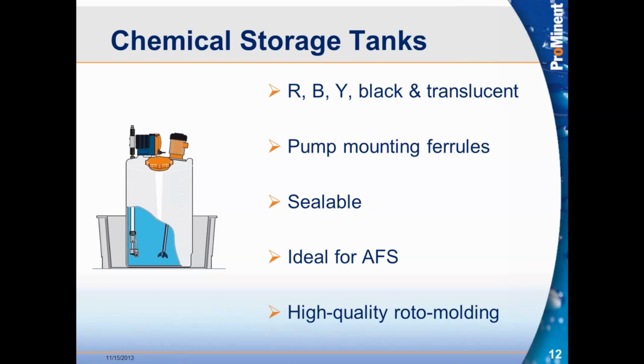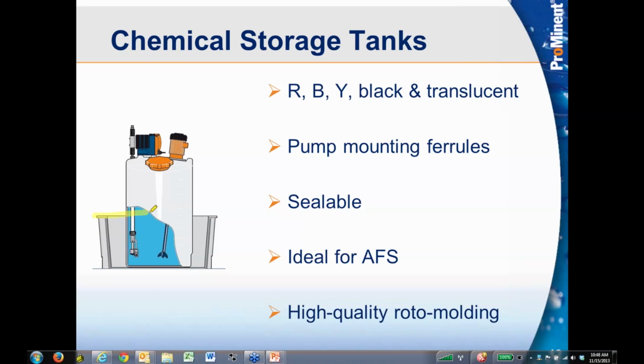Now, the only downside, if there is a downside, is that our tanks are single-walled, and in most cases, municipality, state, whatnot, will require secondary containment. Well, our secondary containment is achieved by placing the tank into a sleeve tank like you see here, like a trough, or you can place our tanks on the catchment pallets that you see frequently. They have a yellow grating on the top with a black catchment bottom. So that can offer secondary containment.